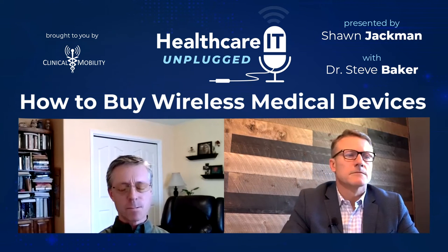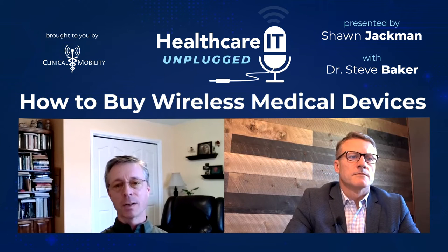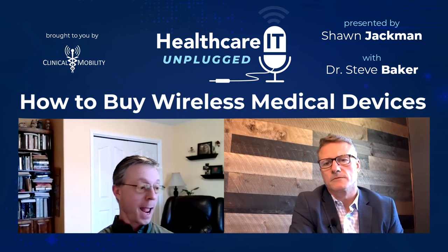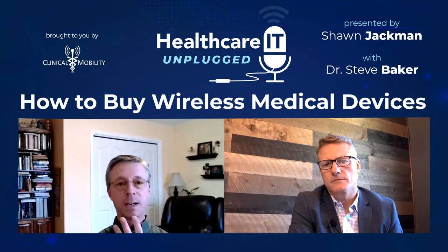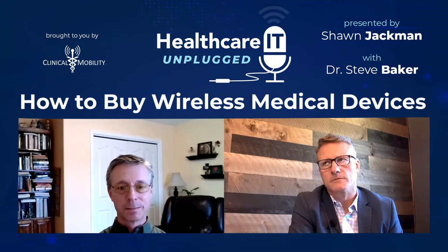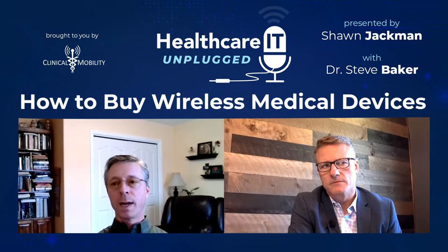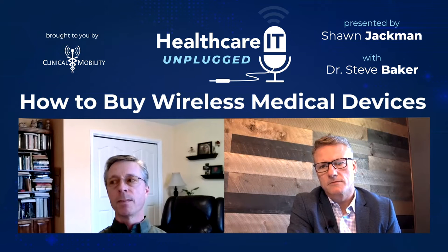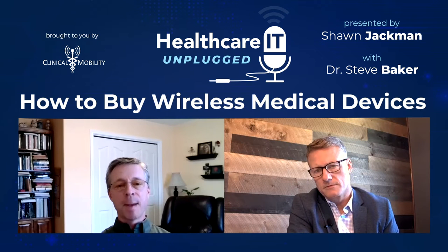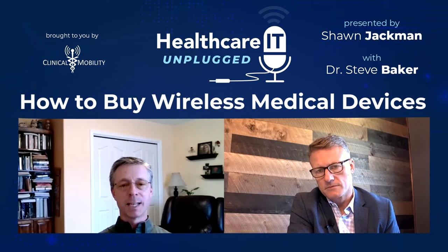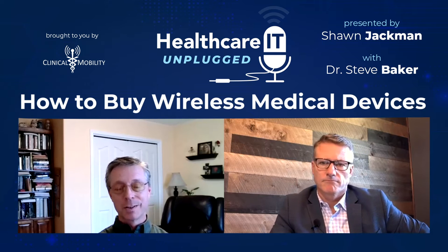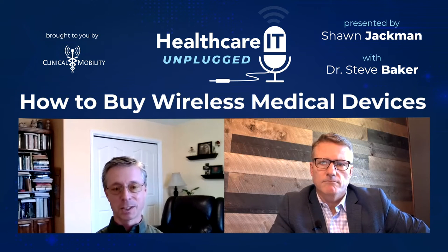So the thing is, I can change out an SpO2 module. In fact, I have a patient monitor with three different SpO2 modules from three different manufacturers. They all have the exact same intended use. The 510K clearance from the FDA is based on intended use. So if my intended use doesn't change, I can change any part on the inside and I don't have to redo my 510K. And that includes radio and system security software.